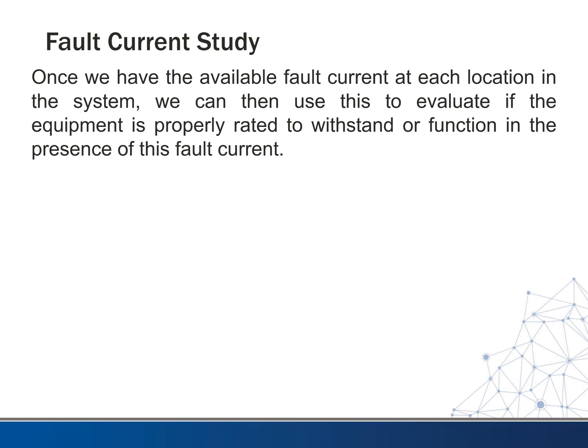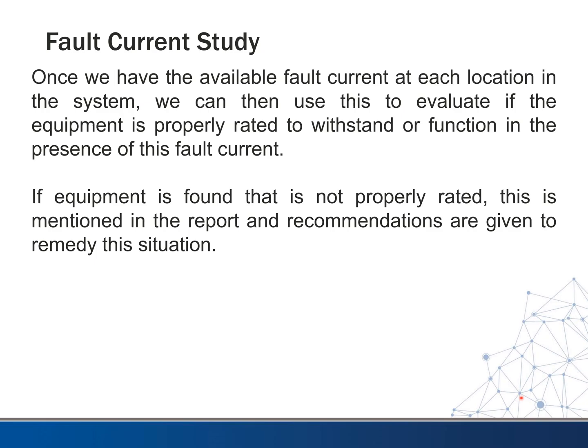Once we have the available fault current at each location, we can evaluate if the equipment is properly rated to withstand or function in the presence of this fault. This is very important — one of the most important calculations we do — because if it's not rated for it, we're going to have a catastrophic event. If the equipment is found to not be properly rated, this is mentioned in our report and we'll usually give recommendations to remedy the situation, such as swapping out a breaker, changing out the entire panel, changing a disconnect, or changing fuses.